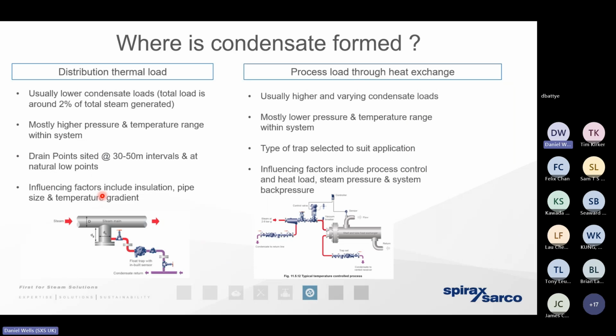So the question really is, where is condensate formed? Simple answer is, well, condensate's formed wherever there's heat loss. So the two key areas where we're going to get heat loss on a steam system, it's on the distribution pipework. First of all, we know that if we're generating steam at a high temperature and a high pressure, 10 bar gauge, 184 degrees, we could be distributing that steam thousands of meters around site in a carbon steel infrastructure. Some of that infrastructure could be outdoors. We could have missing or damaged insulation, and it could be raining. That infrastructure is essentially an oversized radiator. Of course, we're going to get heat loss.